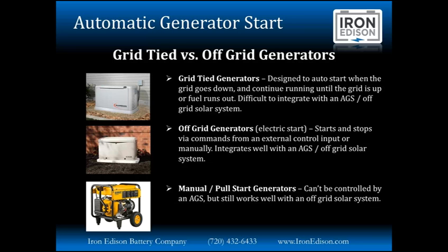There's also manual pull start generators out there. Obviously, they don't have an electric start, so they cannot be controlled by an AGS, but they still work just fine with off-grid solar systems. You just need to go out and start the generator via Armstrong, as we say. You've got to go out and pull the handle, fire it up, and depending on how the inverter is configured, as soon as it sees power from the generator, it'll start using it. So I kind of want to give you that overview of the different types of generators and the advantages or disadvantages to each one.